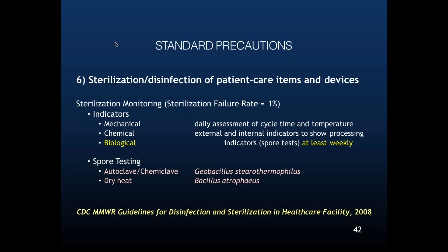Now, we talked about minimum standard. Minimum standard is at least weekly. I get the question a lot. Well, can I sterilize every day? You can sterilize as often as you like, as long as it's at least weekly, right? So if you want to do every day, that's okay. That will cost you more time, cost you more money, but if your patient safety is worth it, I think your patients would appreciate it. The spore test must be one of these two bacteria, Geobacillus S or Bacillus A, and it depends on whether or not you're using an autoclave or dry heat. So it becomes a memorization kind of thing.